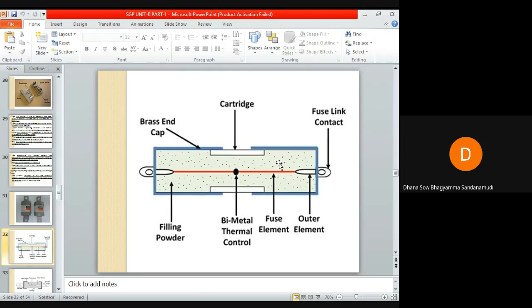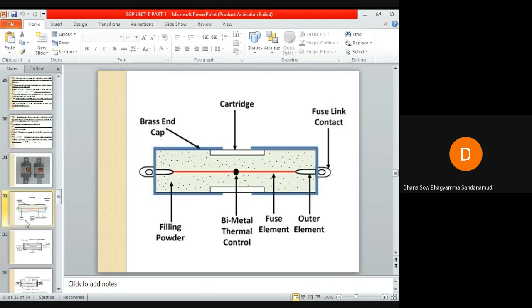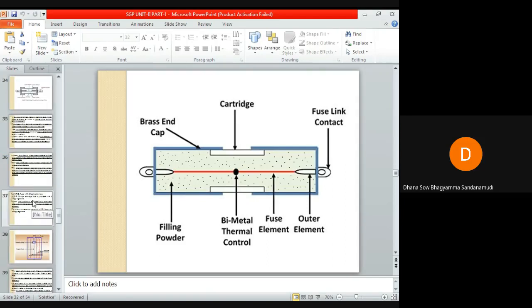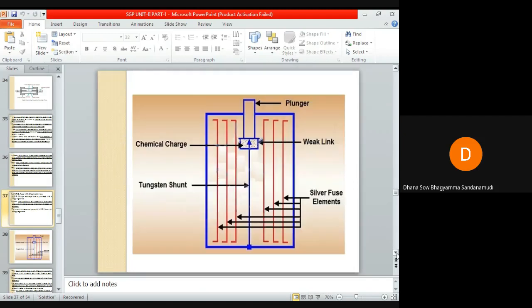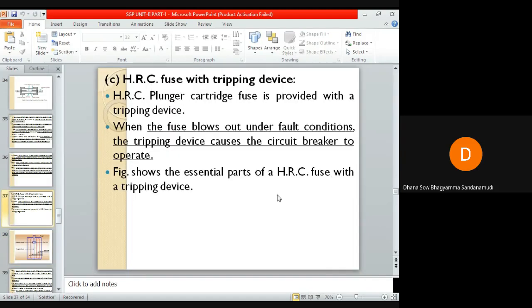One thing that we must remember is, as soon as the fuse is blown out, the fuse melts, and there will be a continuity of fault current in between these two terminals because of the discharge of electrons from one terminal to another terminal. That discharge of electrons is nothing but the arc. So this arc is extinguished due to the chemical reaction of the silver vapors with the filling powder, forming a high resistance substance which will extinguish the arc. So this is all about this HRC cartridge fuse, and next one is HRC fuse with tripping device.